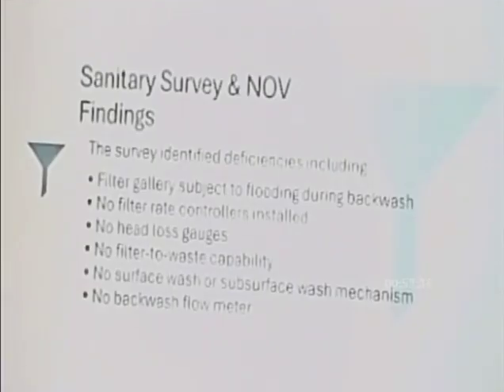We don't have a filter to waste capability, so now after you backwash a filter, DEQ requires you to waste water from the bottom of that filter for a while. So they want to see you backwash it, and then while you're letting all the sand and the anthracite within the filter, you know, it stirs it up, kicks up, and they want to have it settle back down, reconsolidate for a while, and then return the filter to service. That's something that came along later on with EPA rules, with the enhanced surface water treatment rule, that the plant just was not equipped to handle.